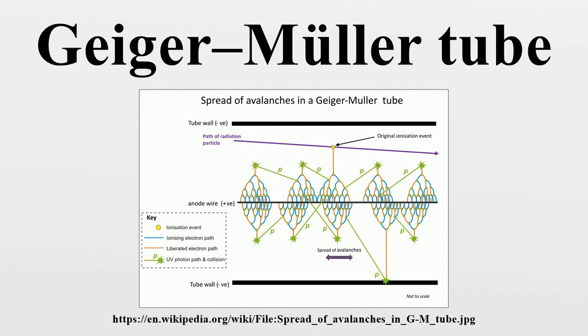Thin-walled tubes are used for high-energy beta detection, where the beta enters via the side of the tube and interacts directly with the gas. But the radiation has to be energetic enough to penetrate the tube wall. Low-energy beta, which would penetrate an end window, would be stopped by the tube wall.